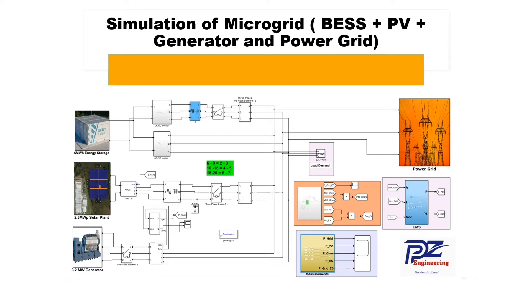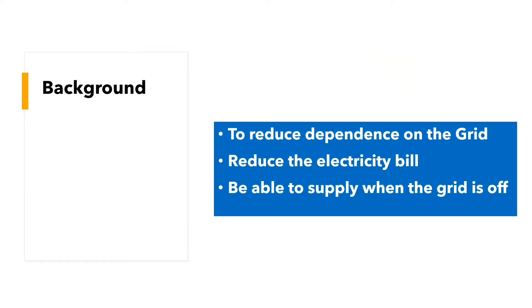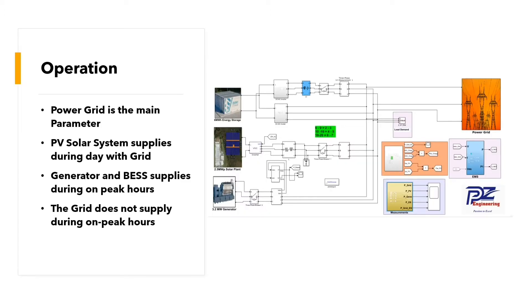The idea to develop this microgrid is to reduce dependence on the grid, reduce the electricity bill, and be able to supply power when the grid is off or during load shedding. The basic operation is: the power grid is the main source, the PV solar system supplies during the day with the grid compensating, and the battery energy storage system supplies during on-peak hours when the grid does not supply.